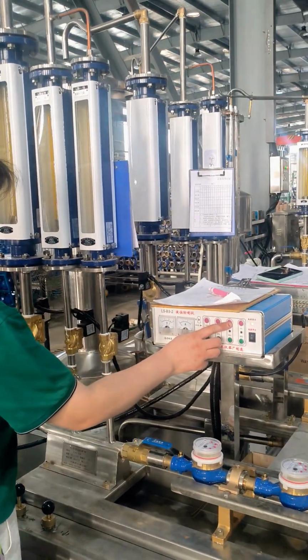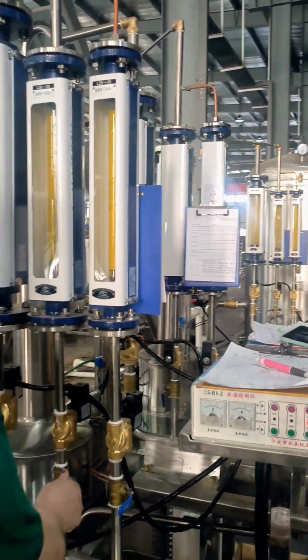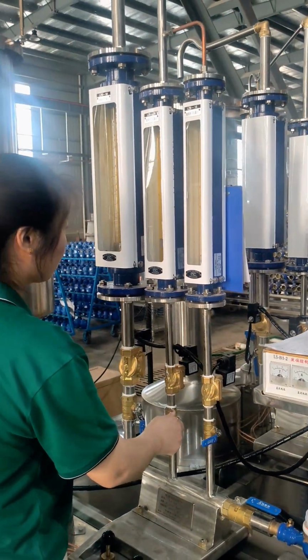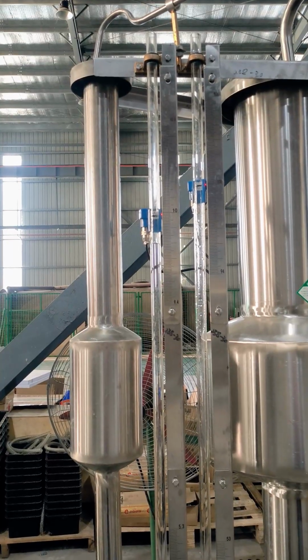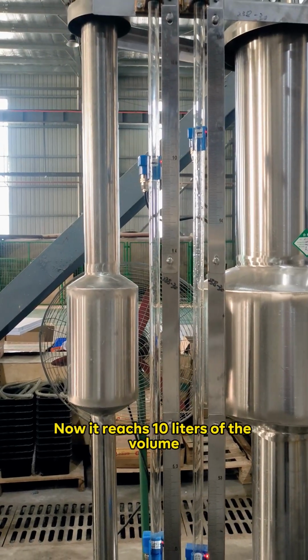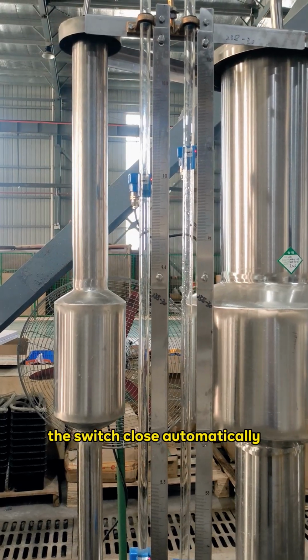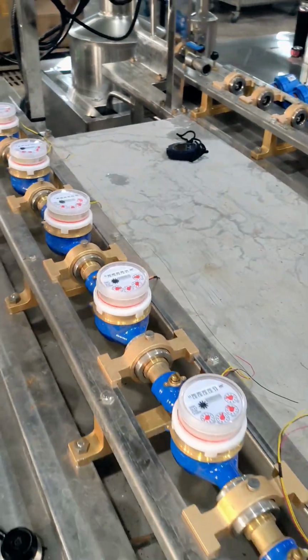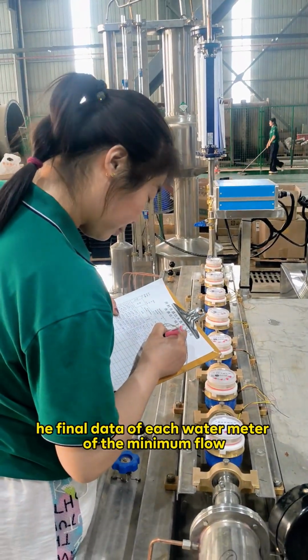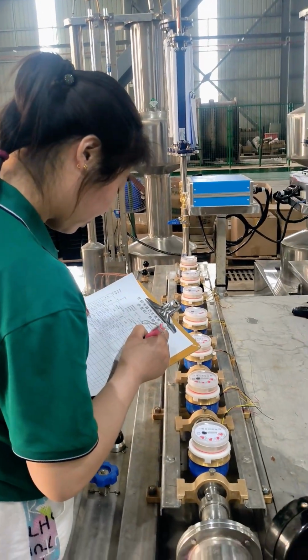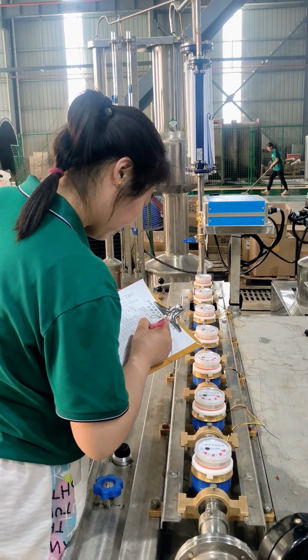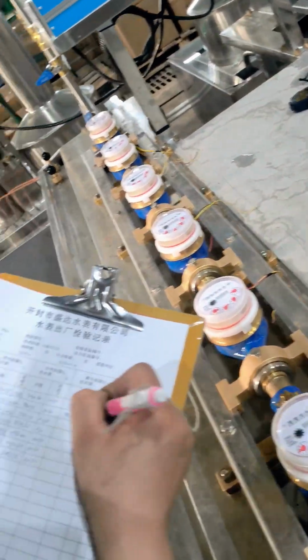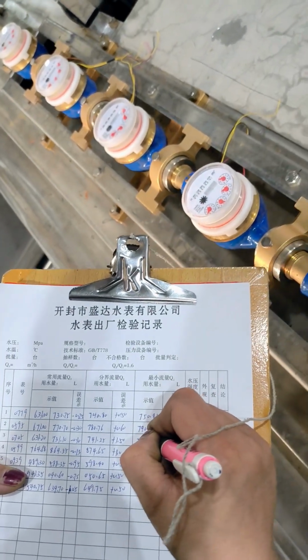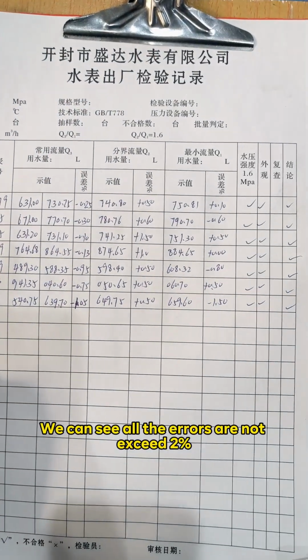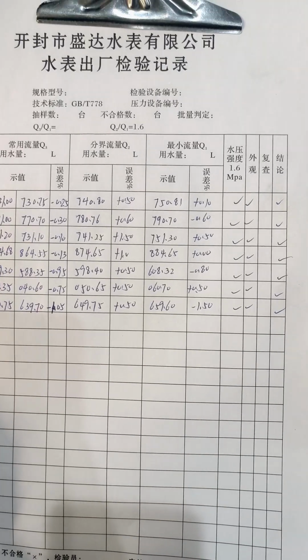Now we start to test the minimum flow. And now it reached 10 liters of volume. The switch closes automatically. We can see all the water meters stop. And now we record the final data of each water meter for the minimum flow. And we can see all the errors do not exceed 2%, and all the water meters pass.